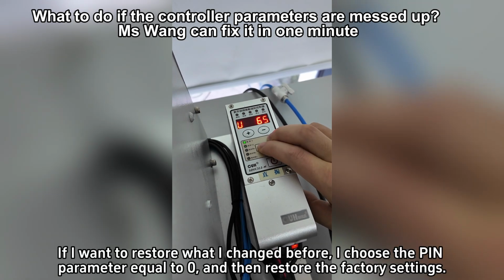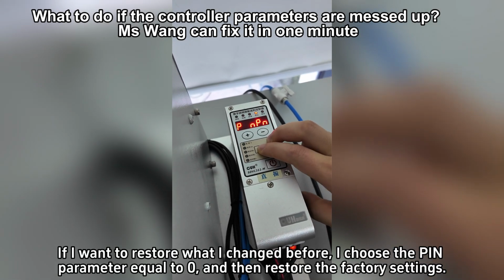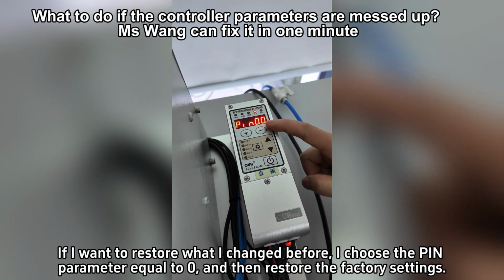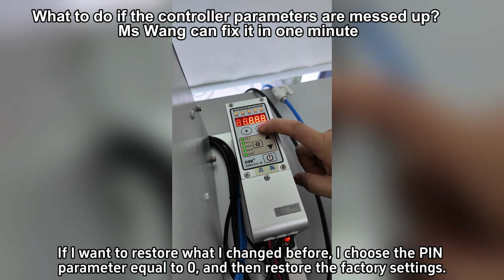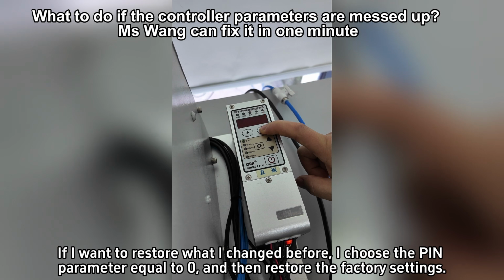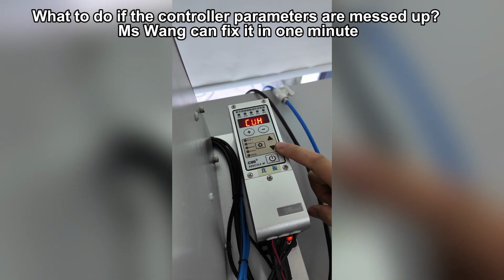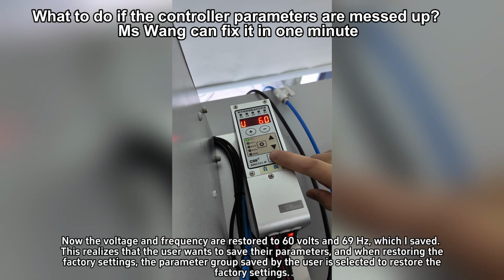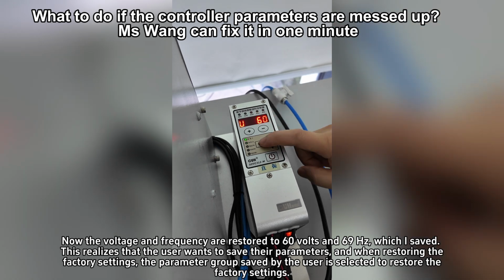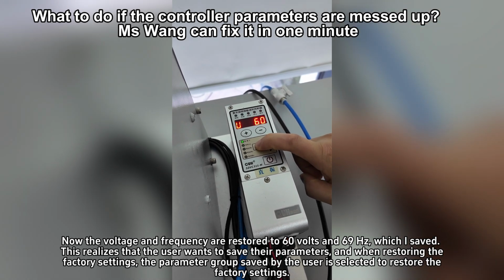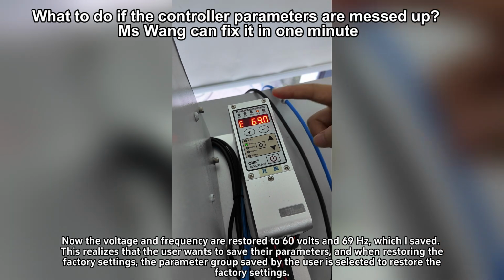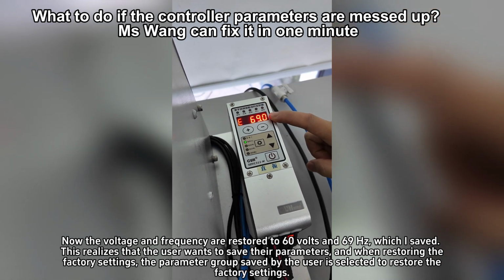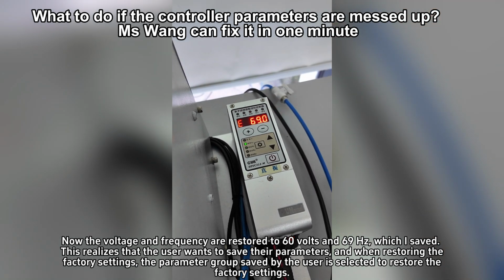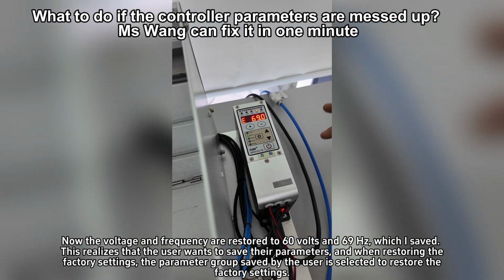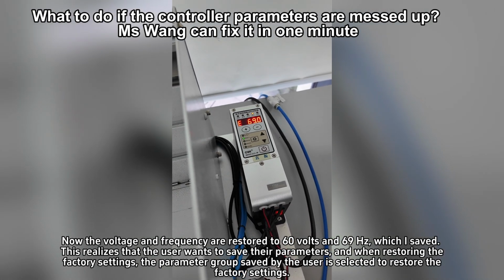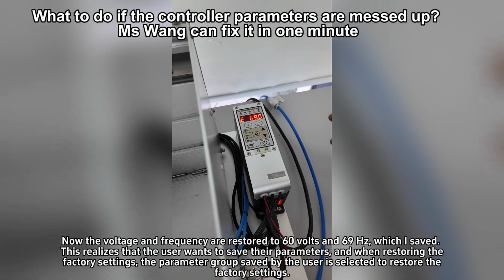If I want to restore what I changed before, I choose the pin parameter equal to 0, and then restore the factory settings. Now the voltage and frequency are restored to 60 volts and 69 Hz, which I saved. This realizes that the user wants to save their parameters, and when restoring the factory settings, the parameter group saved by the user is selected to restore the factory settings.